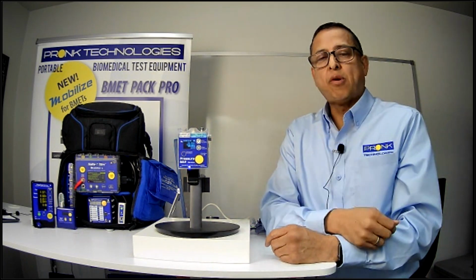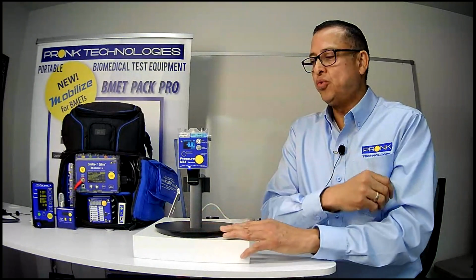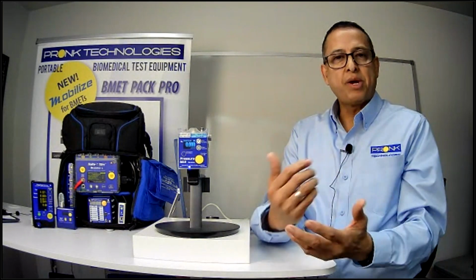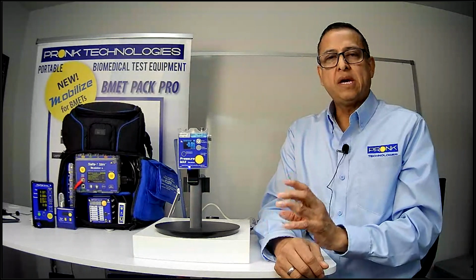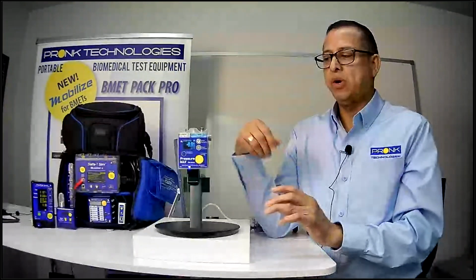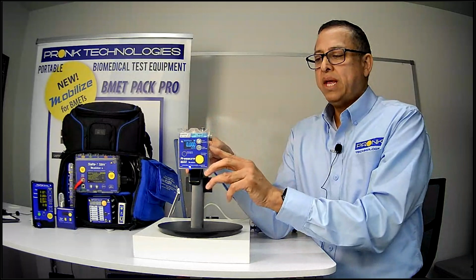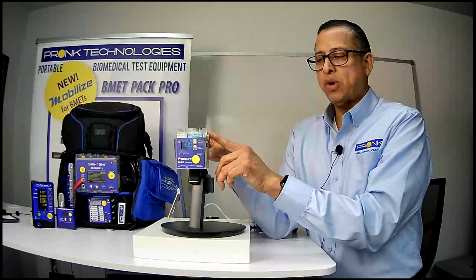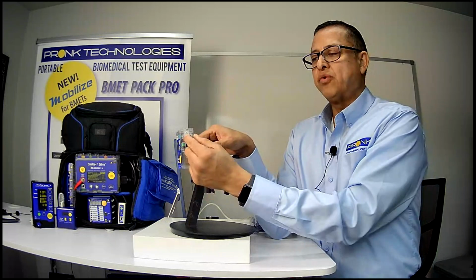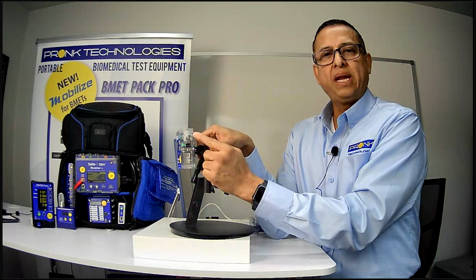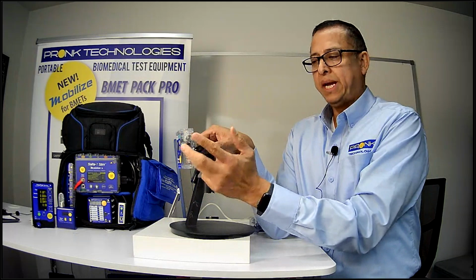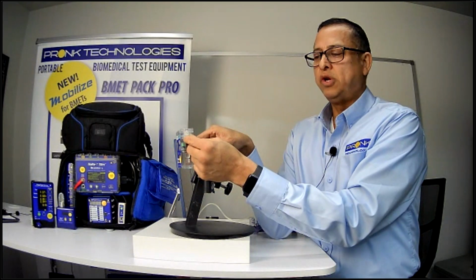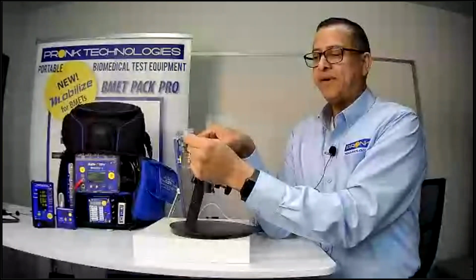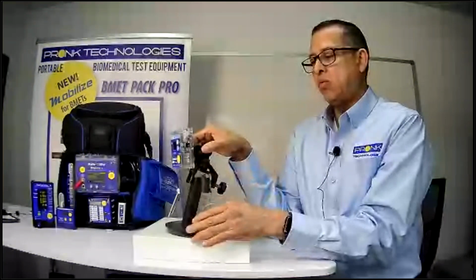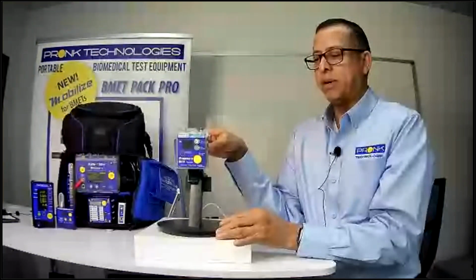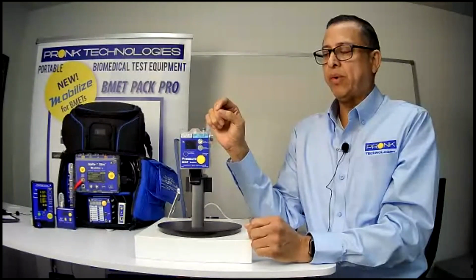The other thing that's a big issue in the marketplace is having the ability to test fluids. A lot of pressure meters are available, they're great, but oftentimes you're not able to utilize them for testing fluids. Well, we've designed into the wide port the ability to test fluids or gas or air, and we have incorporated a thumb screw here so that you can bleed out the fluids, bleed out the air bubbles, so that you can be sure to get accurate pressure measurements, and of course drain fluids when you're doing your testing. So it's a really great benefit being able to test fluids along with regular air pressure on devices, because we know that's a common need. So you're able to do that with the wide port.